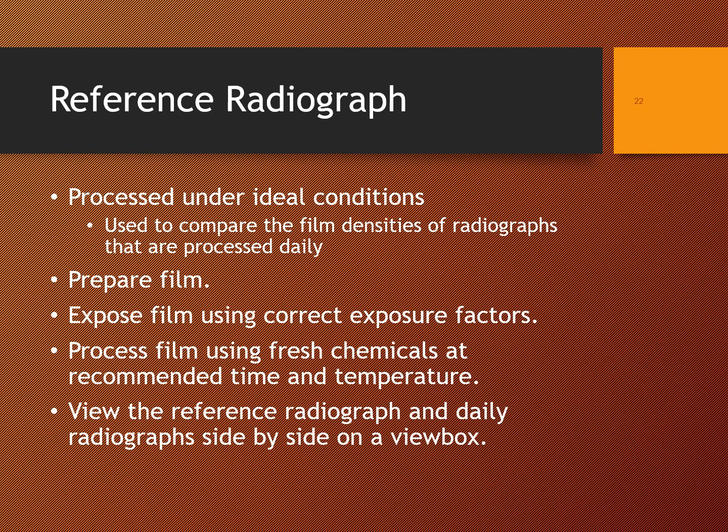Okay, so the first test is a reference radiograph. It's when you go through and pick out a radiograph that you've taken in the past that is like the perfect radiograph. It has the right amount of density. It has to be processed with the same machine, obviously, but we want to make sure that it's a wonderful radiograph. It looks exactly like it should as far as contrast and density and things like that.